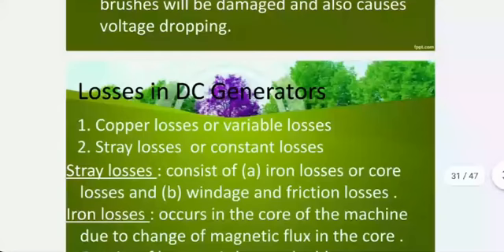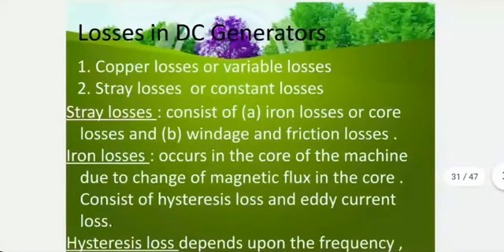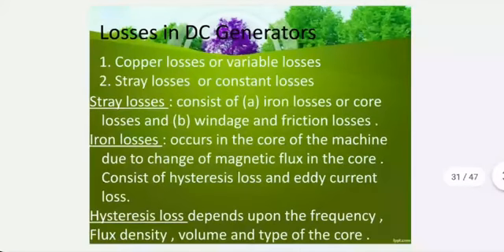A lot of losses are similar to what we saw in transformers, but one extra thing is friction loss and also windage loss, because we have rotation involved, so wind will also have an effect and may produce some losses. Friction will be there for sure, and friction losses have to be accounted for. I don't have equations for them, but we generally know, based on experience, how much loss of voltage will occur because of one pair of brushes -- that number is generally known to us based on measurements.